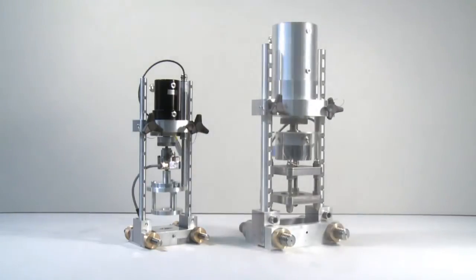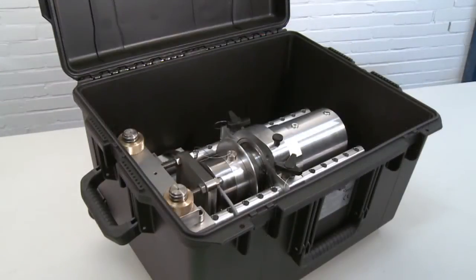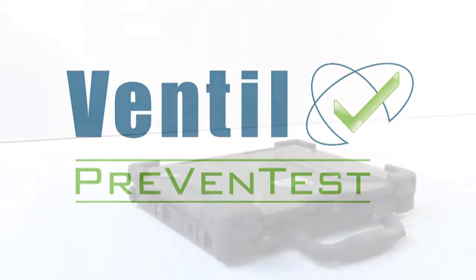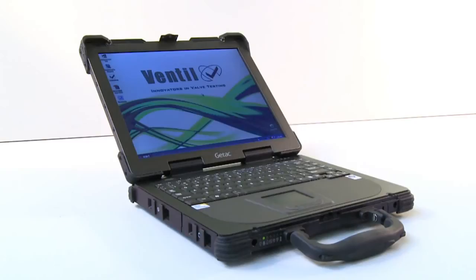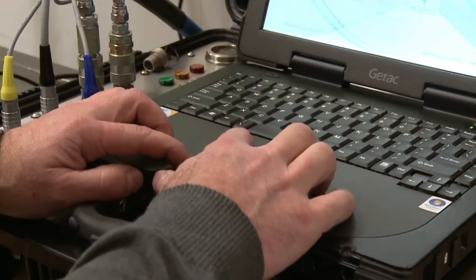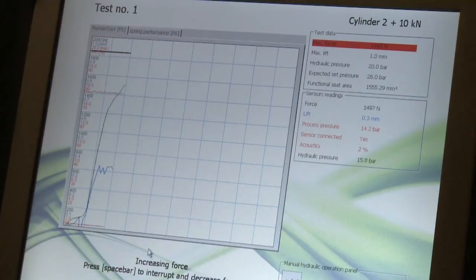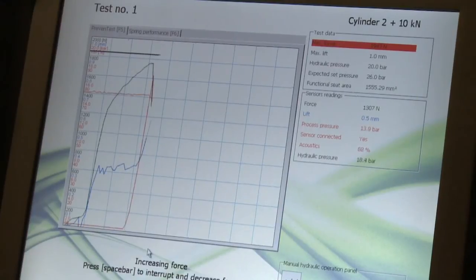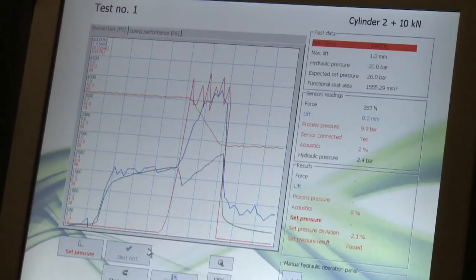The optional 50 kN test bracket is specially designed for extreme large safety valves and testing these with limited or even no line pressure. All three versions of the PreVenTest system are completed with the unique Ventil computer registration system operating on a robust industrial laptop computer. With the PreVenTest Advance and Advance ATEX, the computer automatically controls the complete test sequence. The PreVenTest LTC is hand controlled, but the computer system still plays an important role by digitally displaying the test values, processing the test results and finally creating unique test certificates.